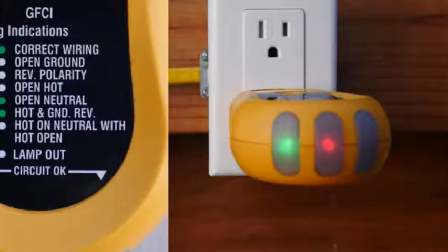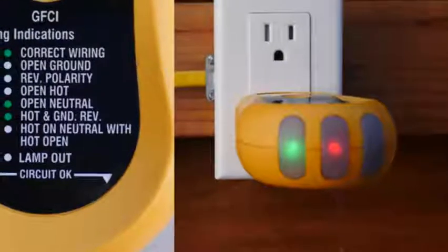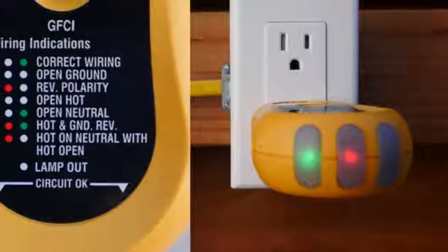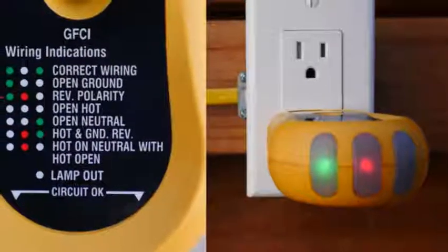On this particular outlet tester, the index shows us that if there's a green light on the left, a red light in the middle, and an open light on the right, then we have reversed polarity. What this means is that the hot and the neutral are reversed on the receptacle.